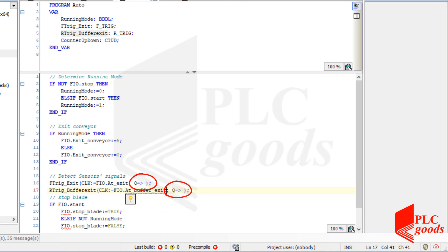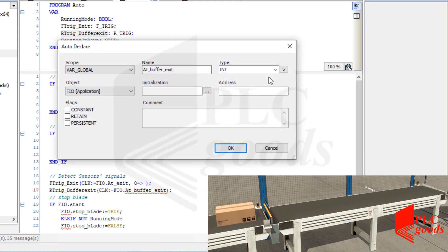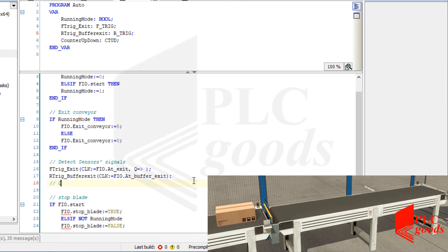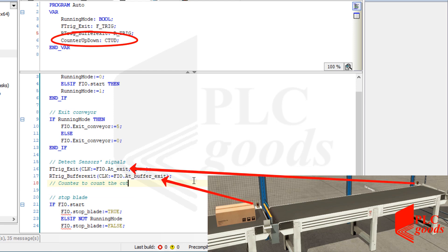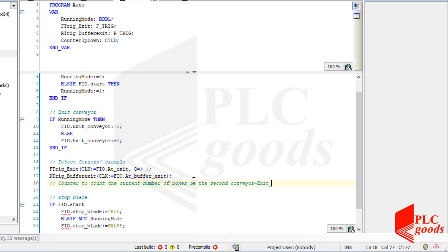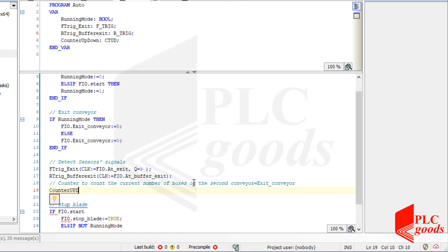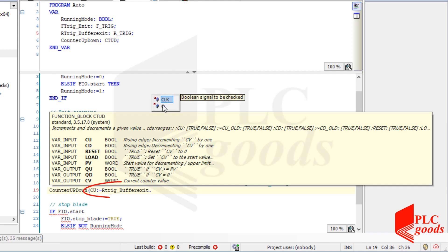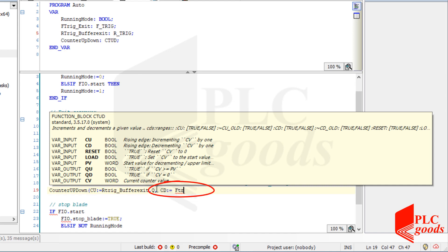These outputs will be used later, therefore I don't need to specify any variable for them, or even I can clear them. Now let me define this variable that will be connected to the sensor. Now let me use the up and down counter with the produced pulses by these two sensors to count the current number of boxes on the second conveyor, whose name is exit conveyor. As you see, if a defined counter, timer or function is used, Codesys will detect its inputs and outputs and display a message that helps us to write the program.